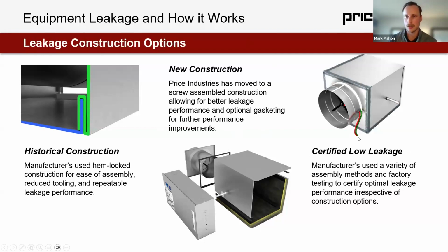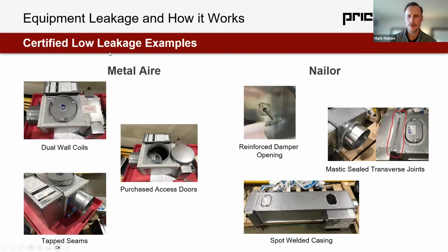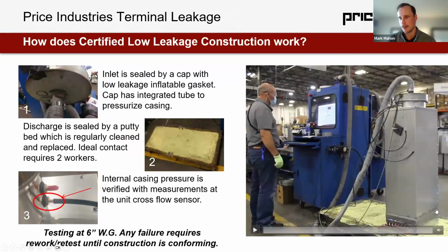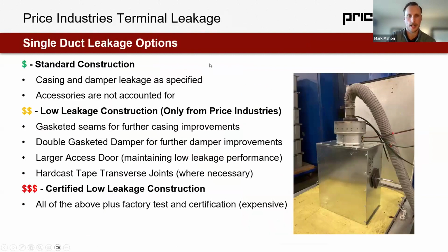The last option is certified low leakage. And that's a really important one, which we were kind of discussing there. So certified low leakage, every manufacturer does it a different way. The goal is just to not make the box leak at all. So Metal Aire is using hard cast tape, purchase access doors, and dual wall coils. Nailor has a reinforced damper opening, spot welded casing, which is very considerable as far as cost of construction, and mastic sealed transverse joints. So they actually seal that themselves. We do something similar. If we go back to this video, you can see mastic sealing. We use screws and gasket. Fortunately, our construction's a little bit more affordable there.